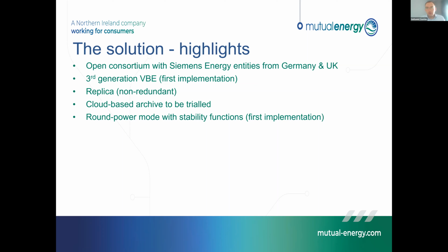In terms of key milestones, because I feel like every HVDC project pushes boundaries in some way, this will be the first implementation of Siemens' third generation VBE. I mentioned the replica, which is an exact replica of the controls that will be at the station, but it will be non-redundant. But it will allow us to model going forward the interconnector's response. It would allow us to adapt to changes and to fault find as issues come up over the operational life. So it will be a really powerful tool. We'll also be trialing a cloud-based archive of TFR records and some of the SER warning messages that would allow access remotely from the station.